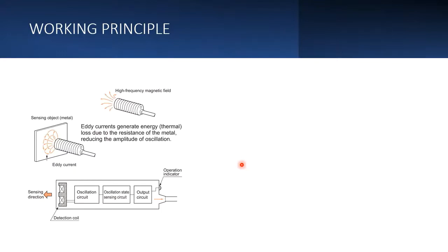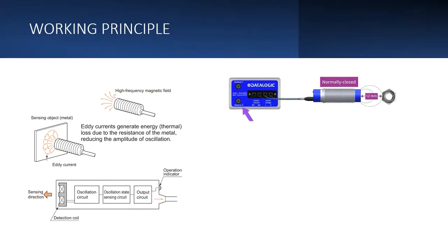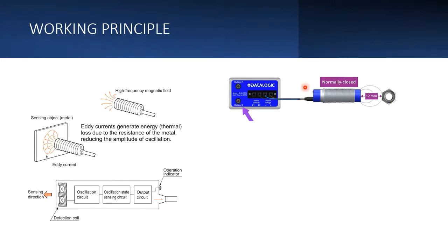How much distance can this sensor sense? It depends on the size of the sensor and how strong a high frequency magnetic field it creates — the higher the magnetic field, the longer the distance it can cover. Here you can see a steel nut with a 12 mm sensing range. As soon as the nut comes within this range, the sensor gives a signal on the back side. As soon as it moves away, the sensor turns off.